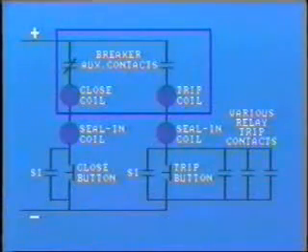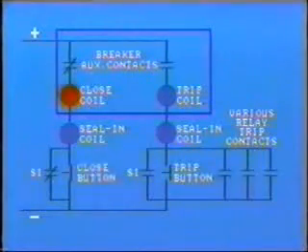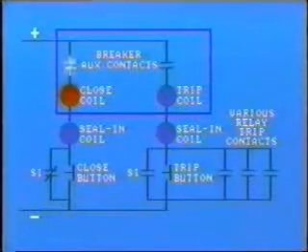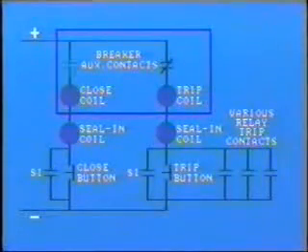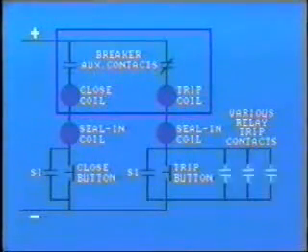A typical control circuit for the breaker is shown here, as discussed in earlier tapes. The breaker closes when the closing coil is energized by this push button. Once the breaker is closed, the control circuit is de-energized by this breaker auxiliary contact. In order to trip the breaker, the trip coil must be energized, and this can be achieved by pressing the manual trip button. In addition to this, several protection relays are connected to close contacts in this tripping circuit, and so trip the breaker and stop the motor.